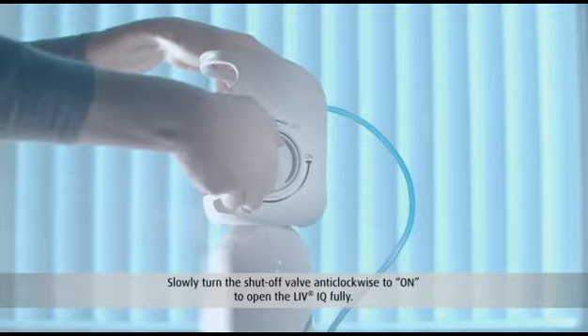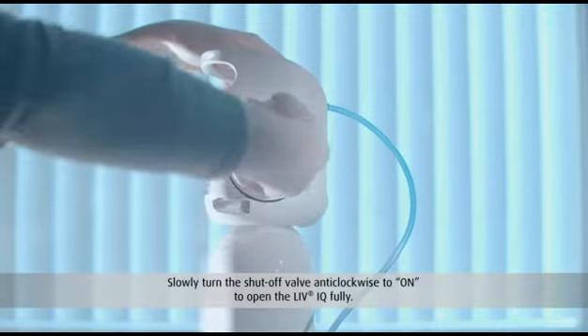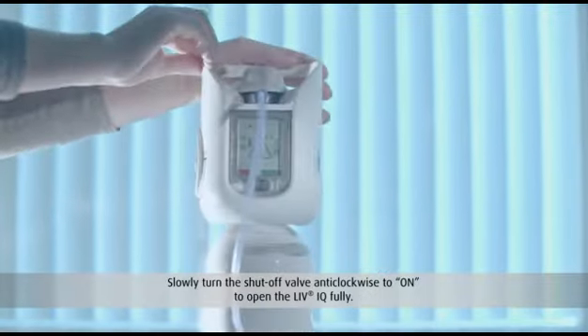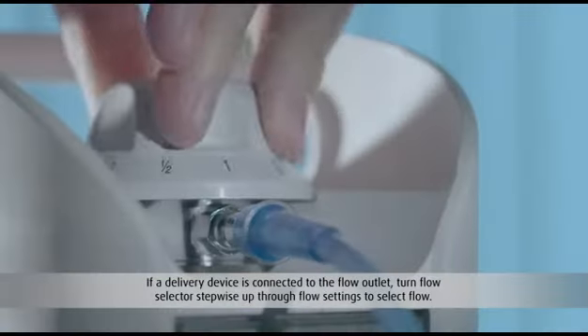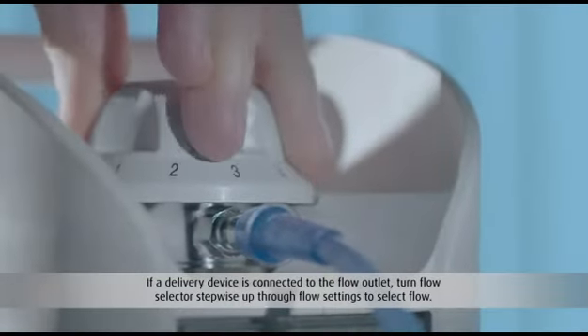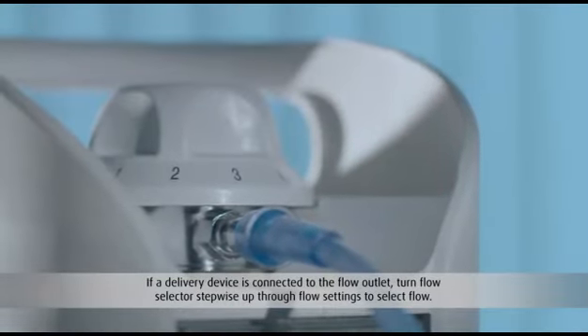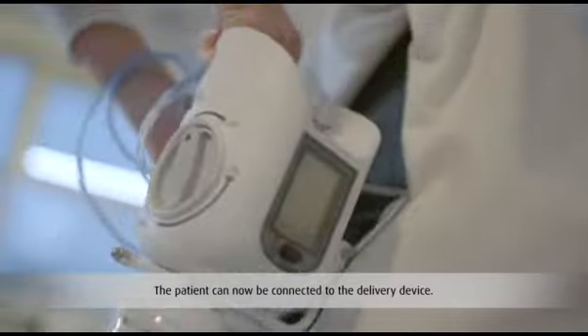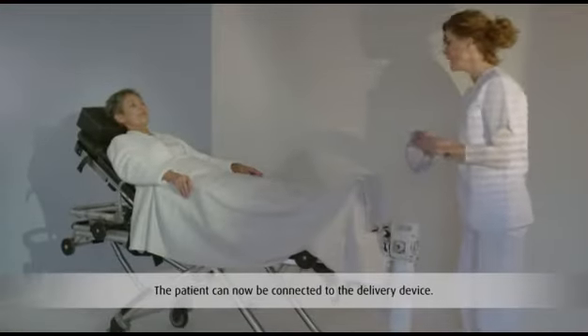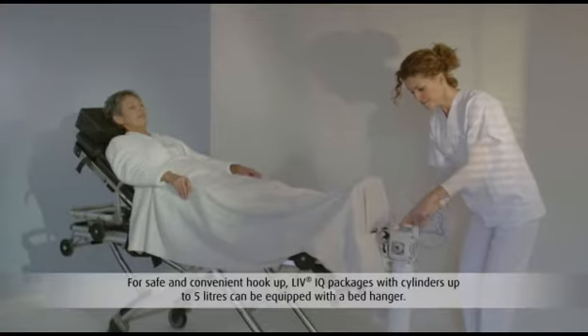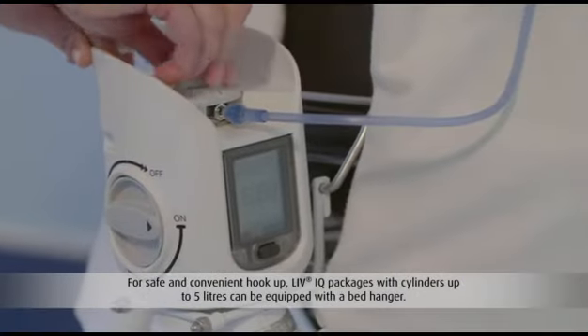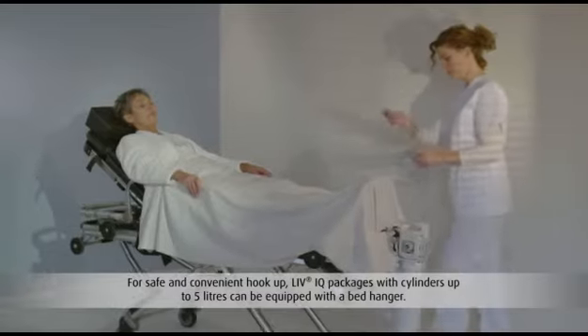Slowly turn the shut-off valve anti-clockwise to on to open the LIV IQ fully. If a delivery device is connected to the flow outlet, turn flow selector stepwise up through flow settings to select flow. The patient can now be connected to the delivery device. For safe and convenient hookup, LIV IQ packages with cylinders up to 5 litres can be equipped with a bed hanger.